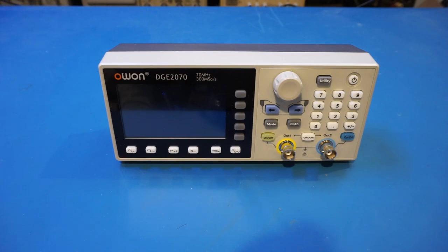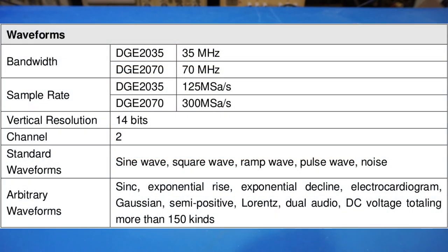The DGE2000 series has two models at the moment. The DGE2070 has a sample rate of 300 mega samples per second, and the highest frequency it can output is 70 MHz when the output waveform is sinusoidal. The other model is the 2035, which has less than half the sample rate at 125 mega samples per second, and the maximum output frequency is 35 MHz.